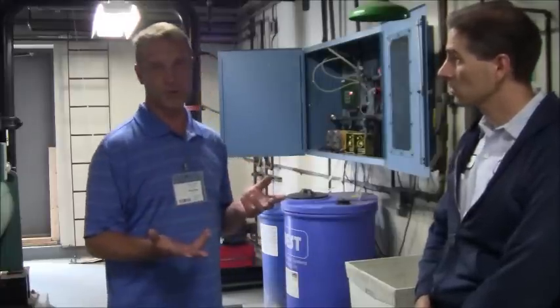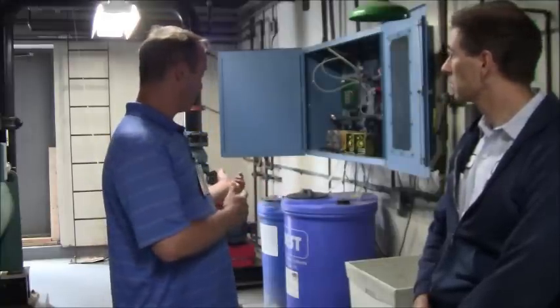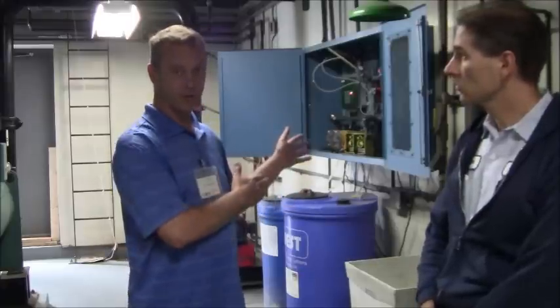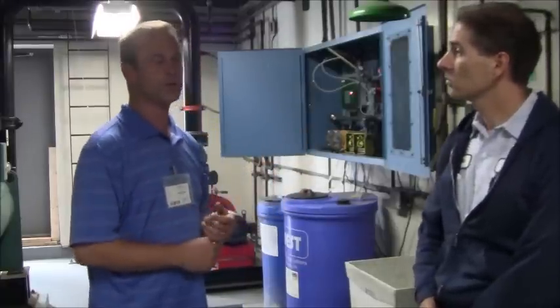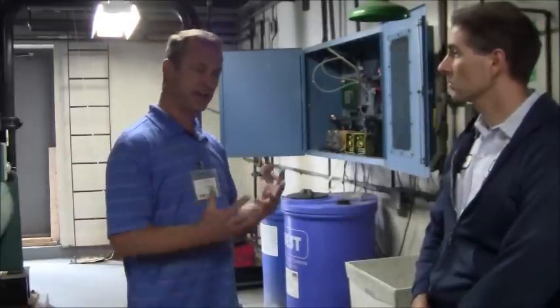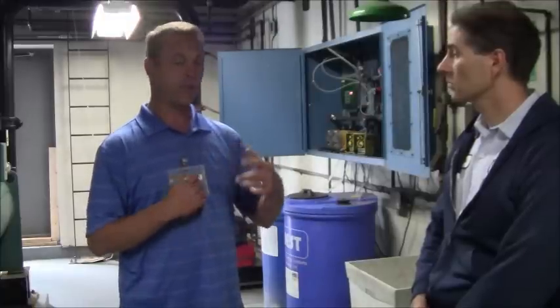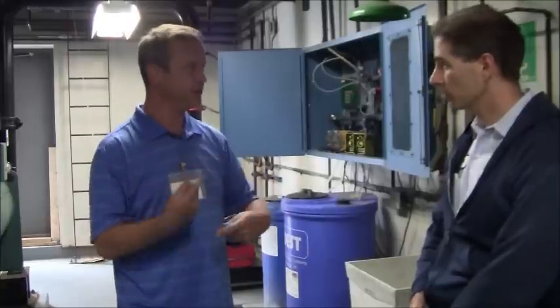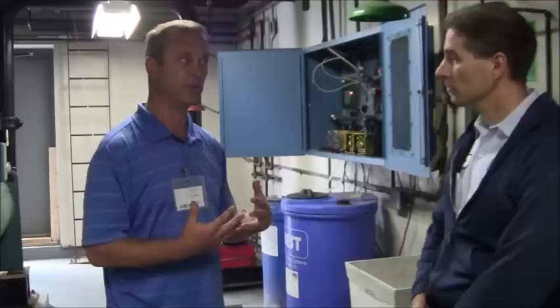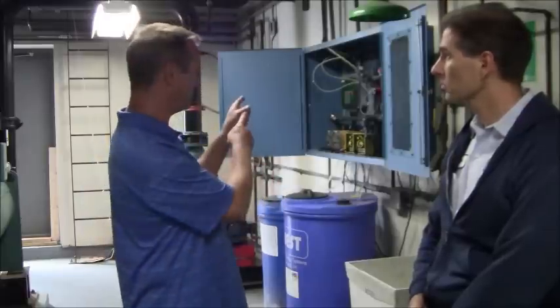Okay. And that's to prevent corrosion and scale in the closed loop system. For an open loop system, the product would be fed based upon the controller for the cooling tower. When we're speaking of open loop systems, you're talking about a cooling tower with evaporation. You're trying to reject the heat out of the building. So that's an ongoing dynamic process versus the closed loop, which is just a tight closed circulating loop. The cooling tower is making up water, dumping water through the bleed valve, evaporating water, so it's a much more dynamic system, and henceforth you need a conductivity controller in order to monitor the water treatment.